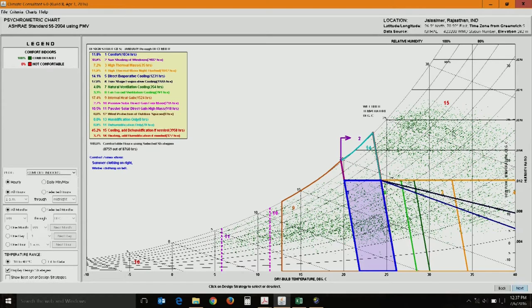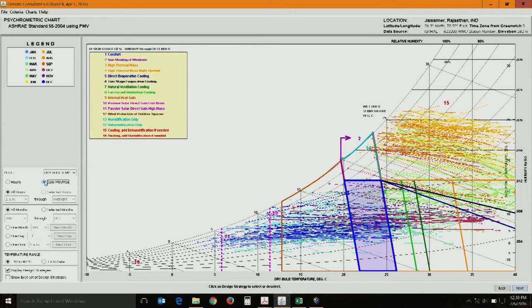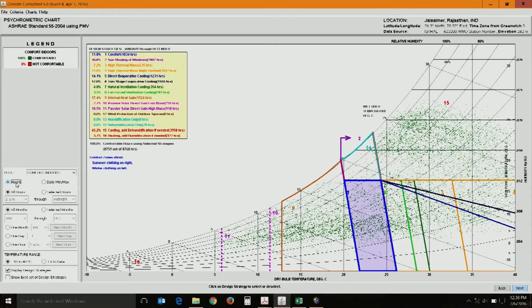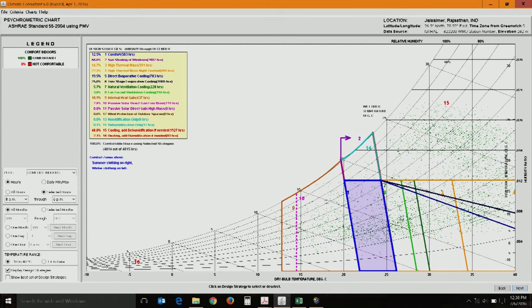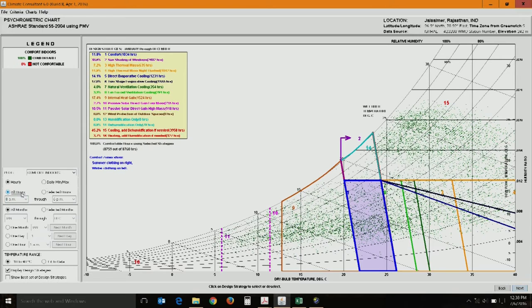Each dot represents a specific time instance. You can plot monthly maximums and minimums or all 8,760 hourly data points. For an office building you can select working hours — say 8 am to 6 pm — giving 4,015 hours of data plotted instead of 8,760. You can also filter by specific months: selecting just January gives you 744 data points for that month in Jaisalmer.